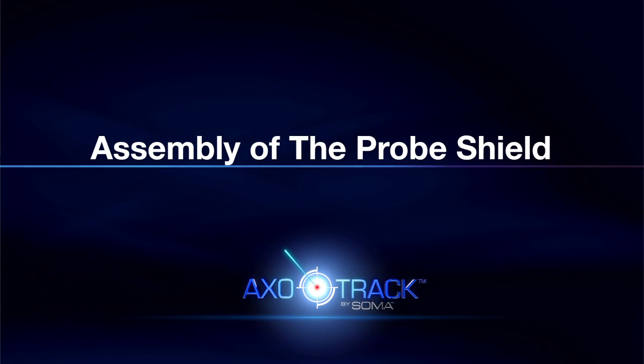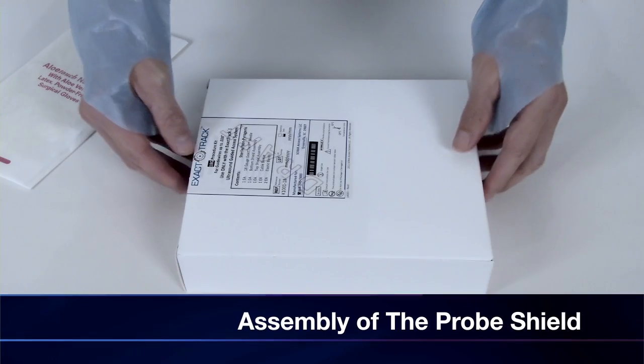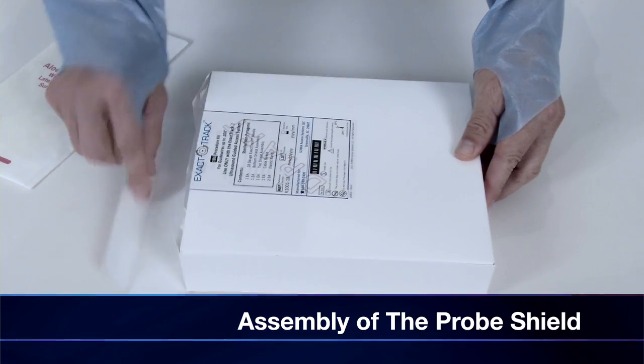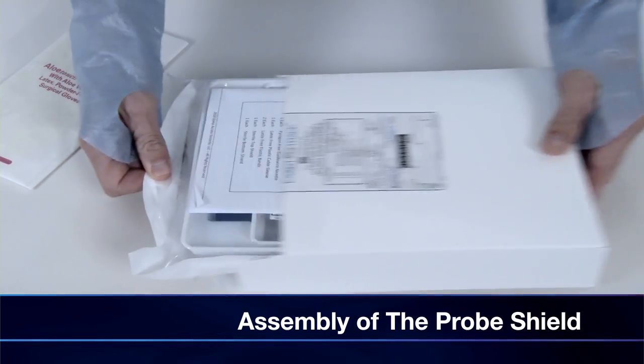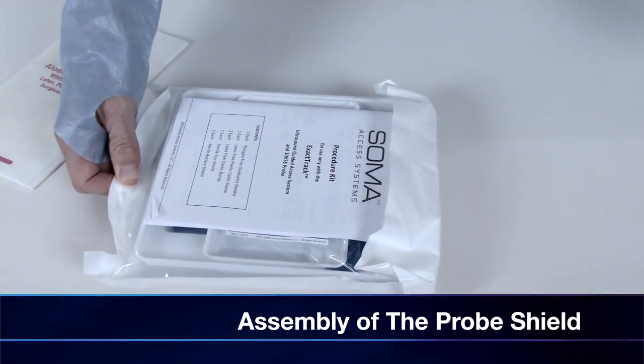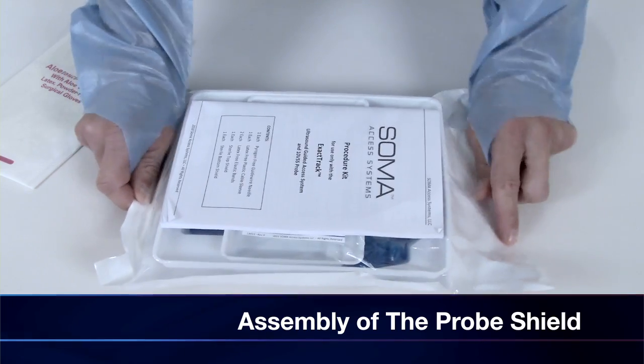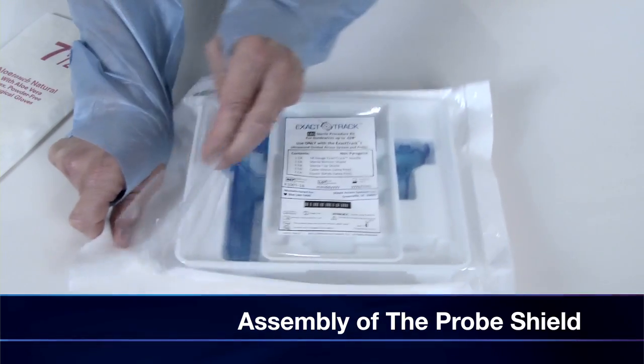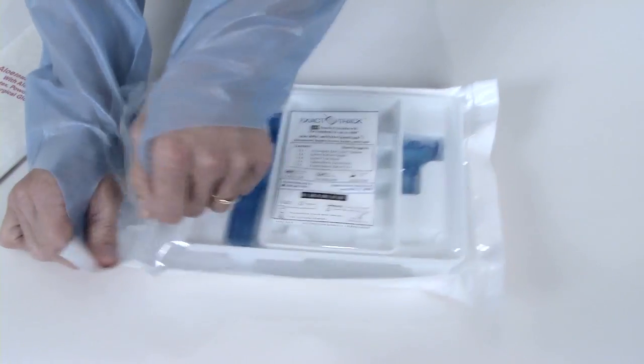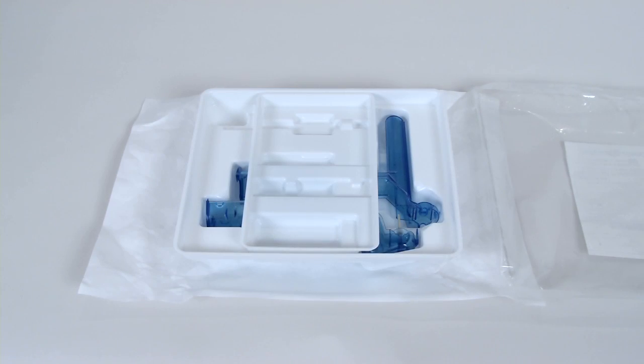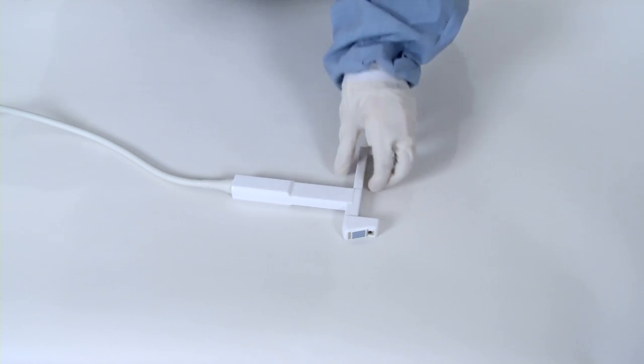Assembly of the probe shield is simple, but requires care to avoid contamination of the sterile field. First, the kit is removed from the box and placed on a stable surface with the white side down. Without touching the kit inside, the clear plastic is peeled away, leaving the tray on the sterile white backing. At this point, the practitioner puts on sterile gloves.